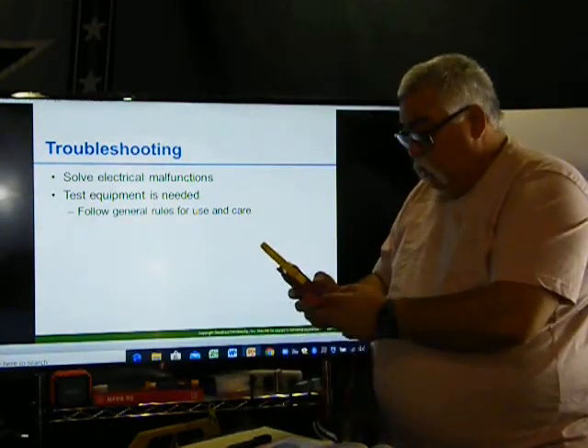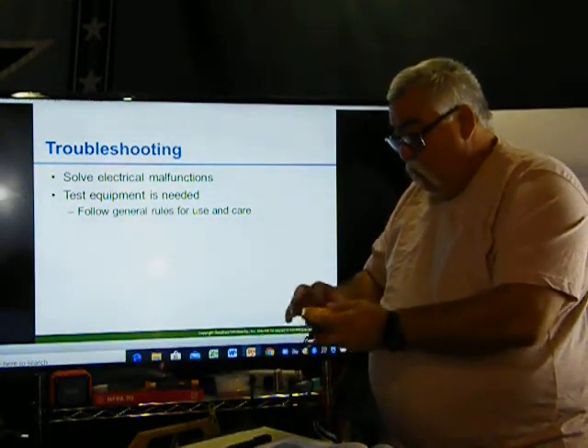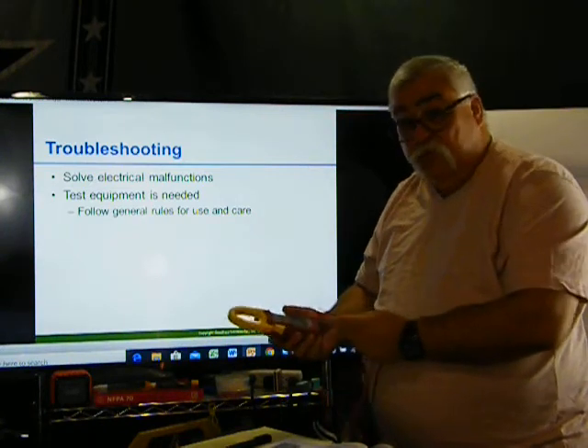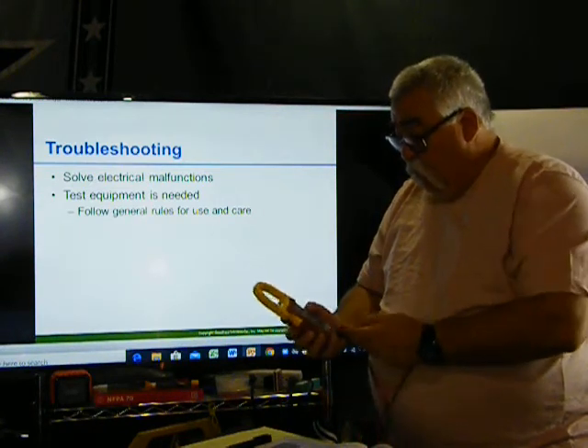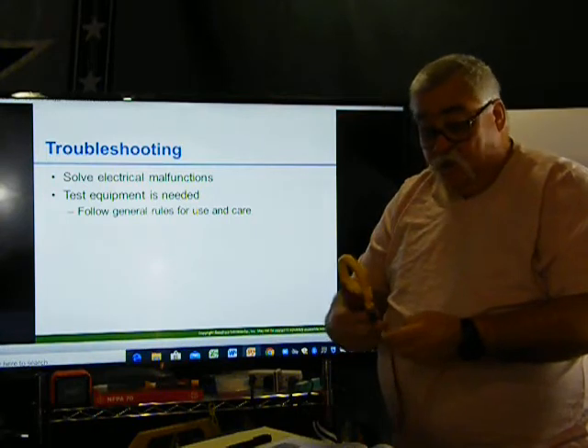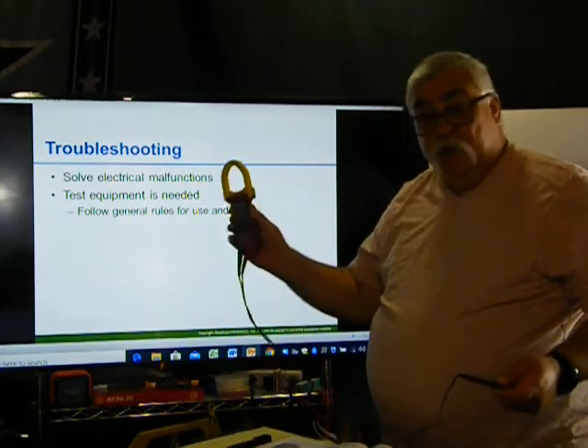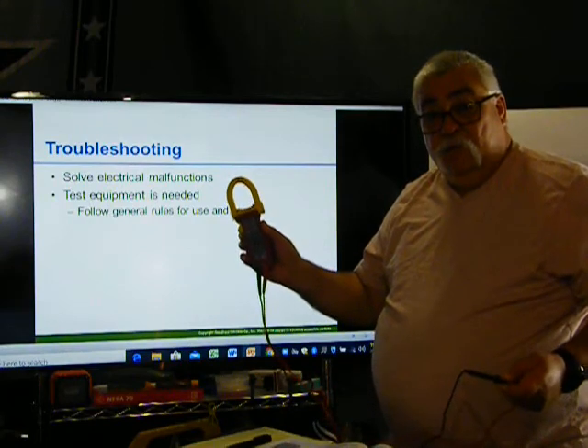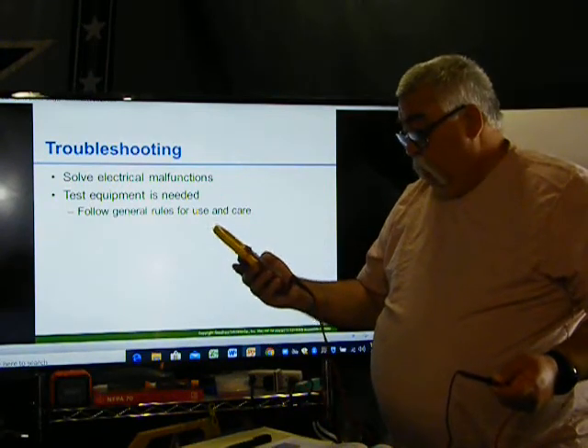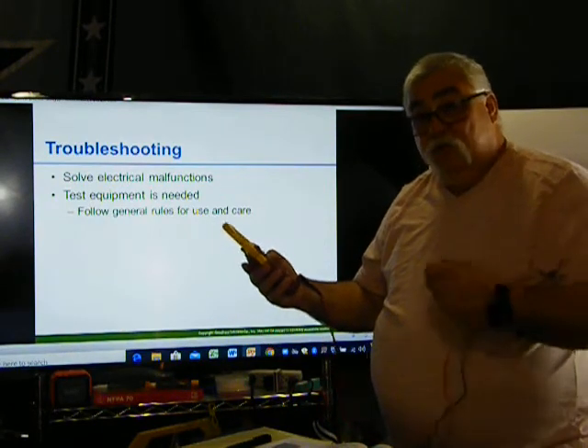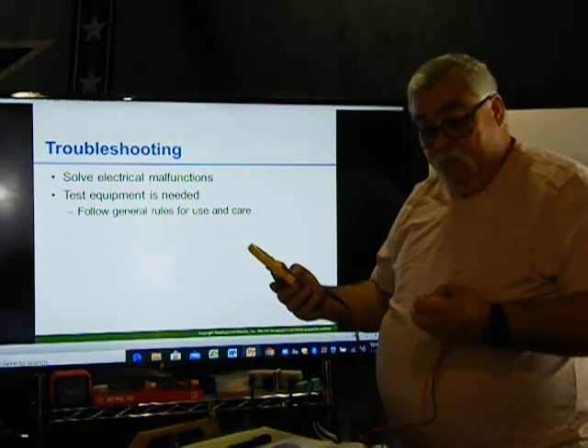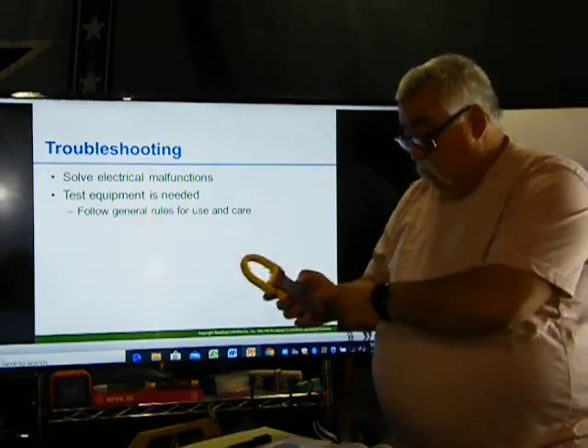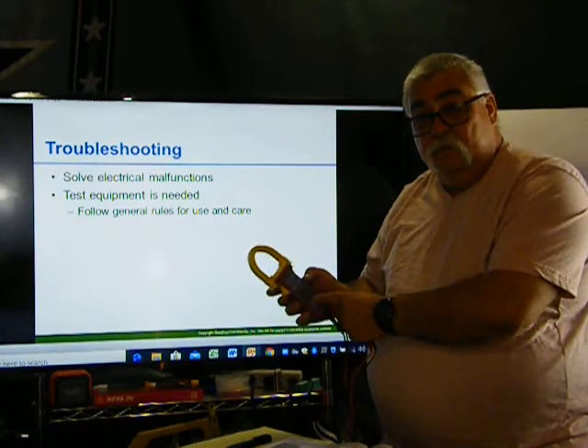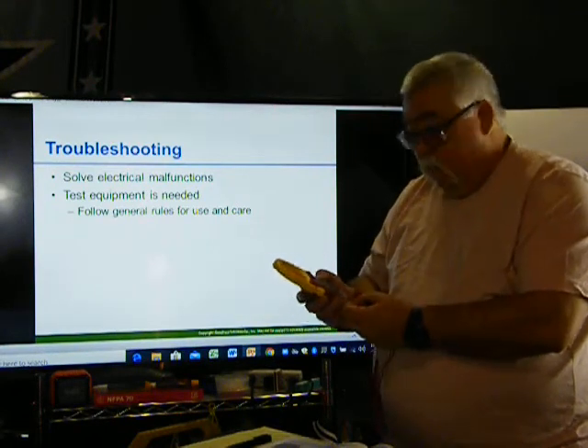Make sure your tester is working properly. Check your battery, turn it on, make sure it comes on. Go to the ohm test. I like to do this every once in a while. Just go and check them to make sure this moves. So it tells me that it's working, and then all of a sudden I'll see it go blank. As soon as I want it to do something, the screen goes blank. That tells me the battery is not working properly.